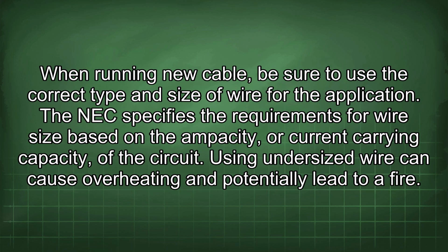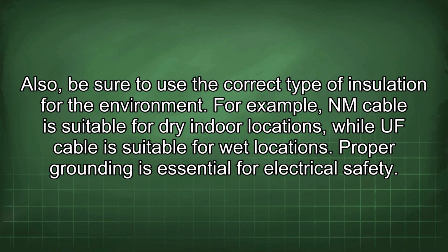When running new cable, be sure to use the correct type and size of wire for the application. The NEC specifies the requirements for wire size based on the ampacity or current carrying capacity of the circuit. Using undersized wire can cause overheating and potentially lead to a fire. Also, be sure to use the correct type of insulation for the environment. For example, an NM cable is suitable for dry indoor locations, while UF cable is suitable for wet locations.